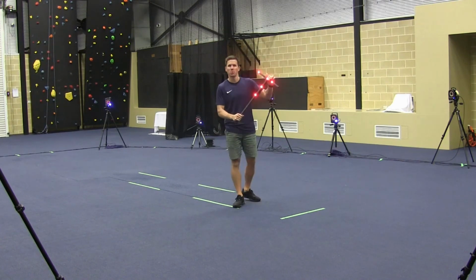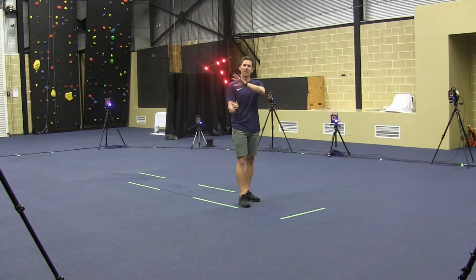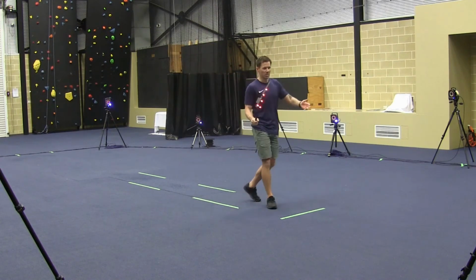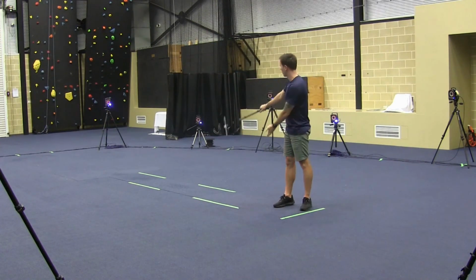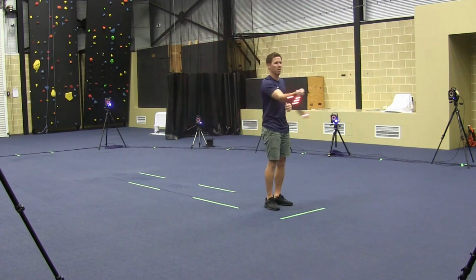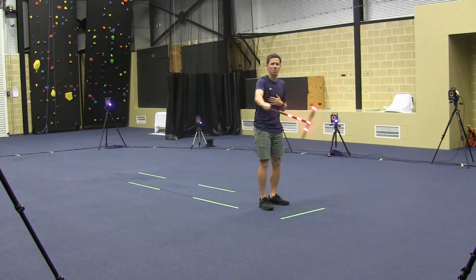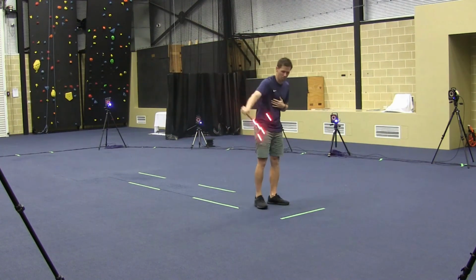So what you want to do is switch it on. Once you've got it on, you basically want to try and move the calibration wand through the exact volume area that your subject's going to be walking through. For example, our subject's going to be running over the 4 platforms in this direction, so I want to make sure that I'm going across every single pixel, essentially, that the cameras are going to pick up with the subject moving through.